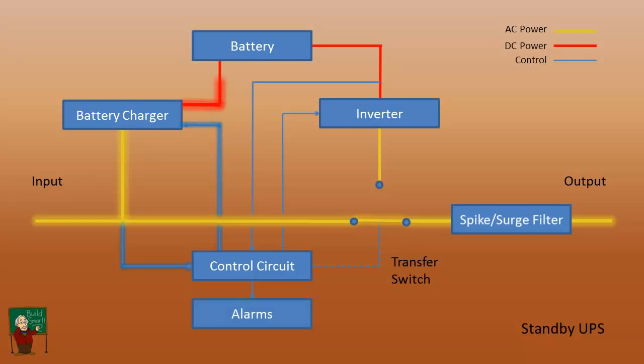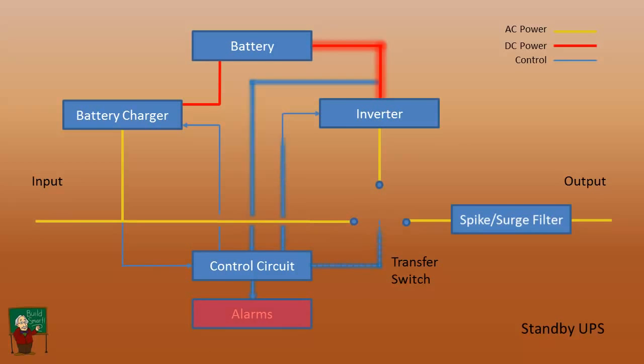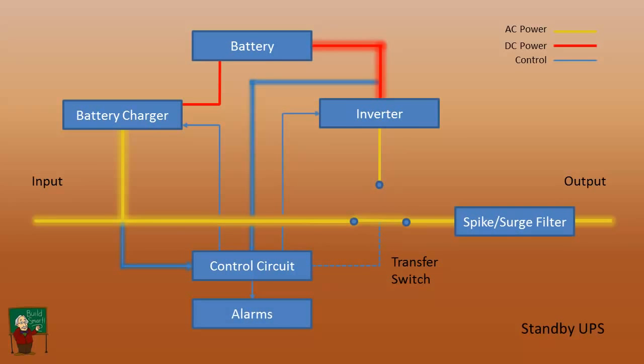The control circuit will turn on the battery charger, which sends power to the battery. When the battery has charged up, it sends out its voltage, tells the control circuit, which is able to shut off the charger. When the power goes out to this unit, we'll see that we set an alarm, and a number of things happen, but basically the control circuit turns on the inverter, flips the transfer switch, and now we have an alarm set because there is no power on the input. So again, going back to our standby mode with a charged battery, we'll look one more time at loss of power, an alarm signal from the control circuit and the transfer switch, and we have the power coming out.